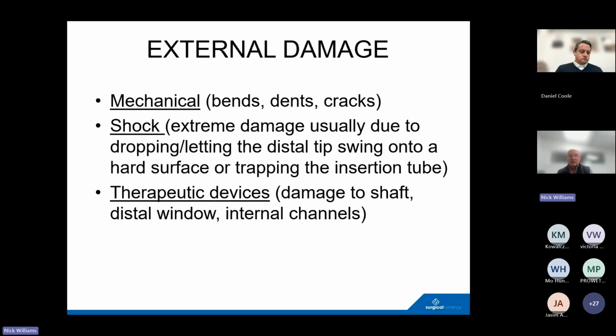Now, externally, there's a lot of mechanical damage. You can smack things, causing shock damage. There are bends, dents, and cracks. They can get cracks in the insertion tube purely because the insertion tube is old and it's being used a lot. Shock damage is usually from dropping it or catching it in something. The classic thing is if you hold a scope like this and you just let the distal tip swing around, do not do that. Make sure you always have the distal tip in the same hand, or you've stopped it swinging around, because obviously if it swings around and hits something while you're handling it, not good.